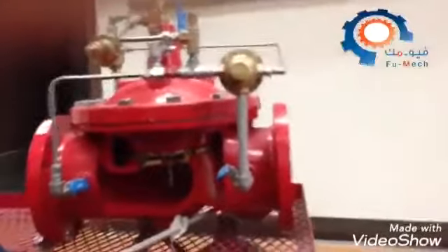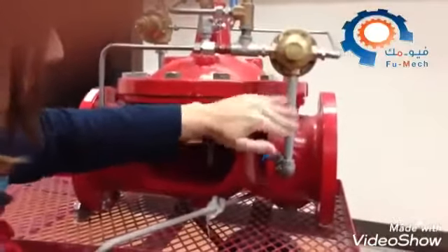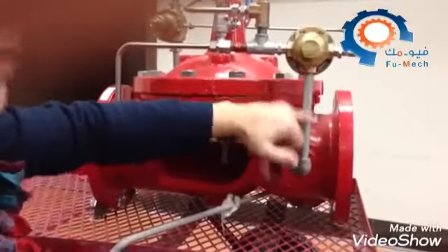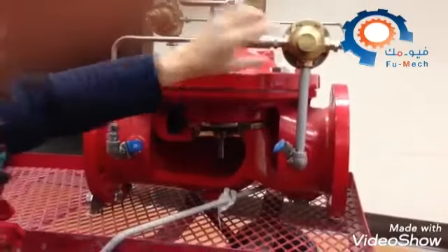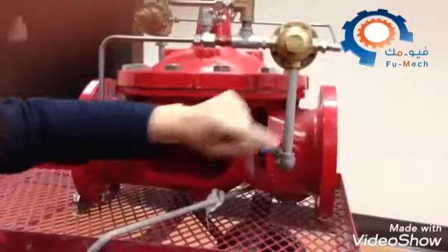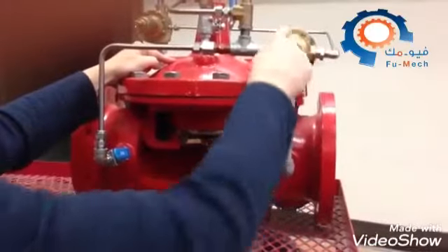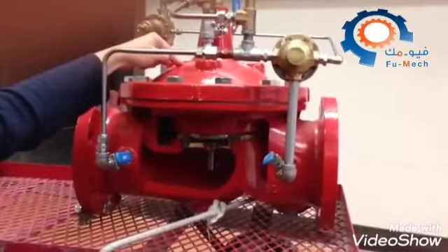It starts pulling water. All of that 0.1 liters per second is going to come off, go through the valve and go out. In addition, because it's wide open, because we've got this great big pipe here, it's going to start pulling water off the top of the valve. So we'll have water coming in from two locations into here and going out. The big valve will open wide. If this fails wide open, this will fail wide open. We don't want that.